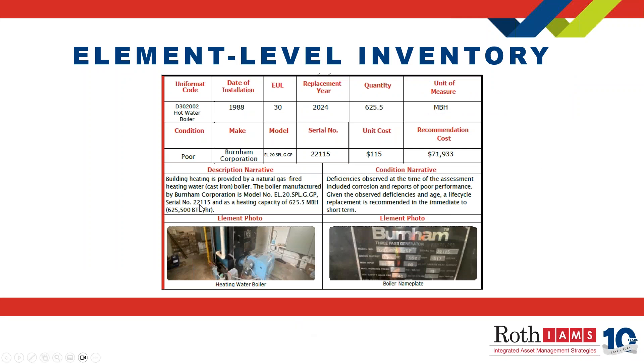Here is an example of an element-level inventory. We go down to Uniformat level four. Starting from HVAC D30, then D3020 boilers, we're now at D30202, which is a hot water boiler. We have date of installation, EUL, and replacement year. You get a quantity — in this case 625.5 MBH — and a condition rating. This is where we gather the make and serial number. You get a unit cost and recommendation cost based on quantity: 625.5 MBH at $115 per MBH comes out to $71,933. You get a description narrative, a condition narrative, and photos including, where we gather make, model, and serial number, a photo of the nameplate if available — giving you both an overview of the boiler and the nameplate.